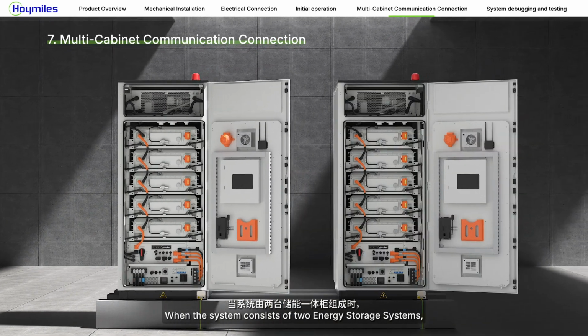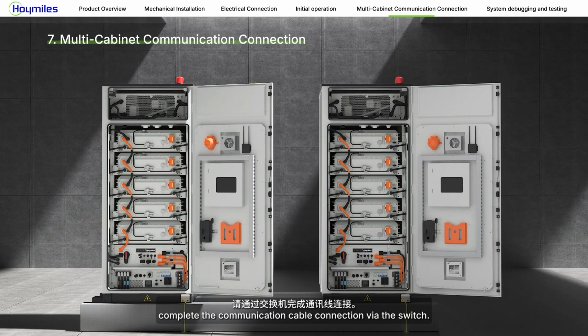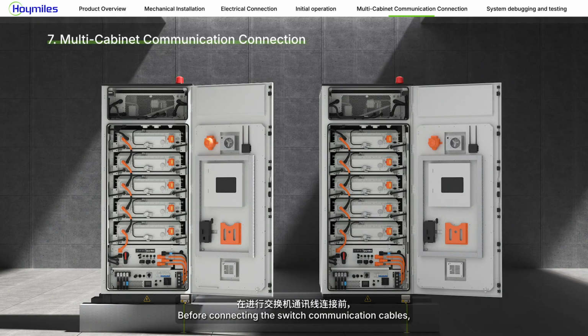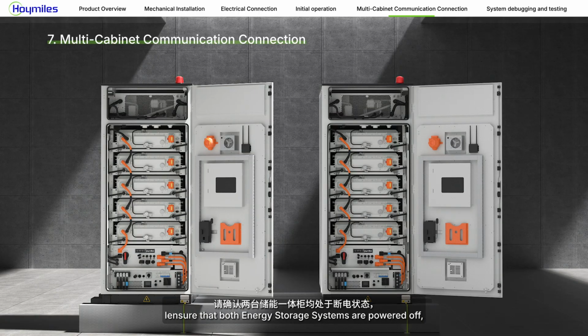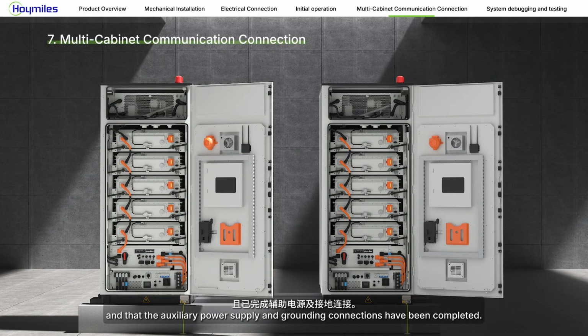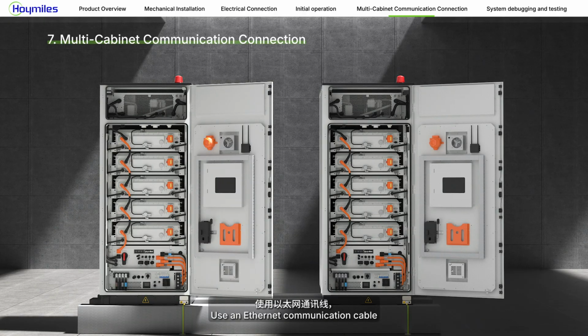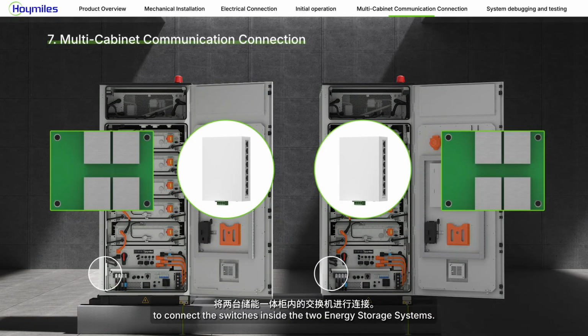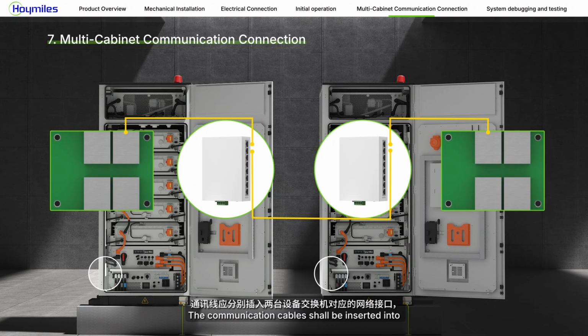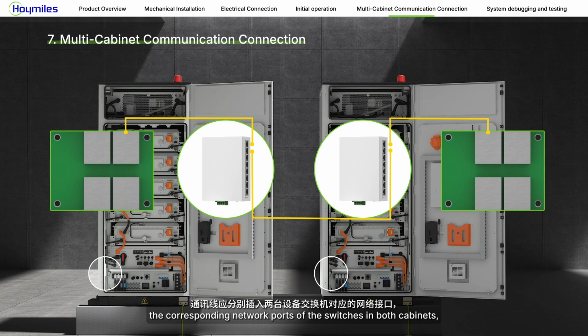When the system consists of 2 energy storage systems, complete the communication cable connection via the switch. Before connecting the switch communication cables, ensure that both energy storage systems are powered off and that the auxiliary power supply and grounding connections have been completed. Use an Ethernet communication cable to connect the switches inside the 2 energy storage systems. The communication cable shall be inserted into the corresponding network ports of the switches in both cabinets, ensuring that the connections are fully seated.